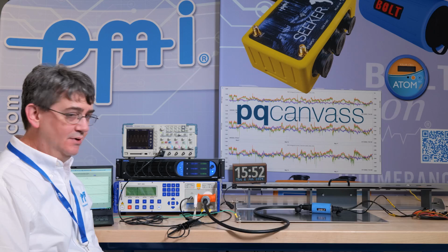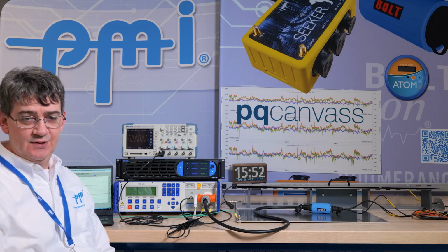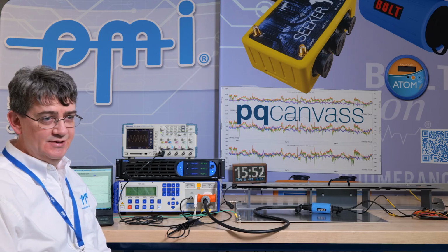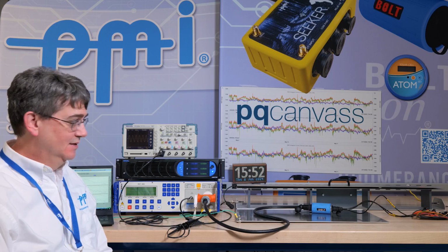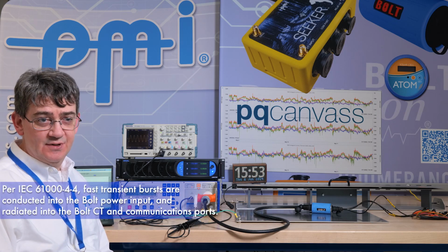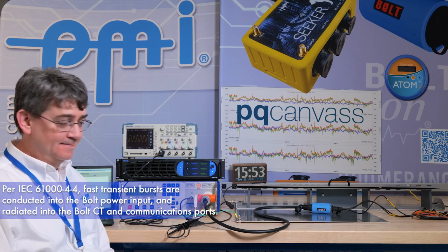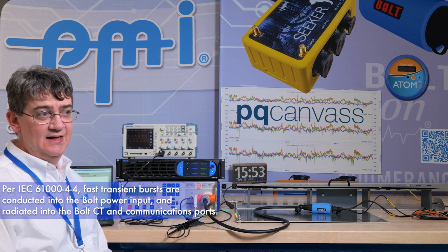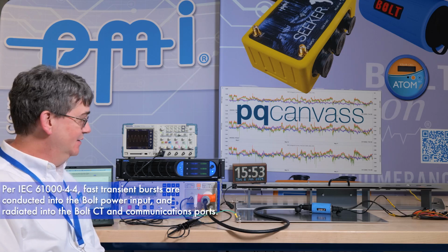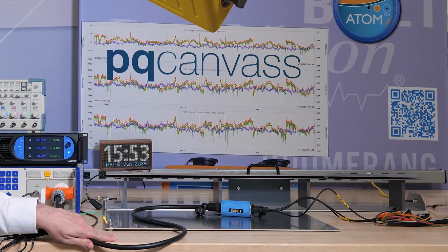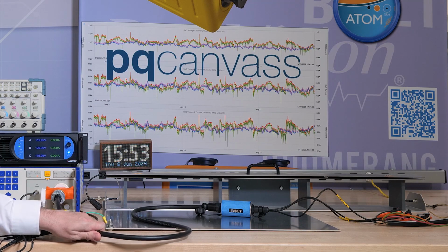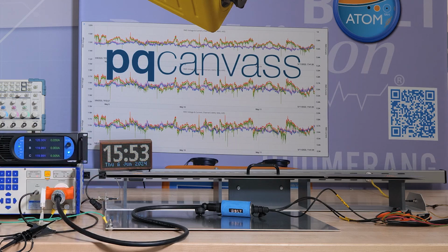Today we're going to test the bolt's immunity to fast burst transient pulses. These are the types of pulses you might find in a harsh industrial environment that are caused by commutation problems in equipment or brush motors or other types of switching transients. And we're using the guidelines of IEC 61000-4-4, which calls for applying pulses both into the power input of the bolt through conductive path and also radiated into communication ports.